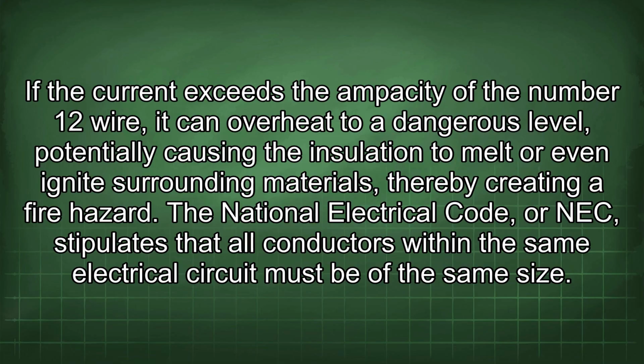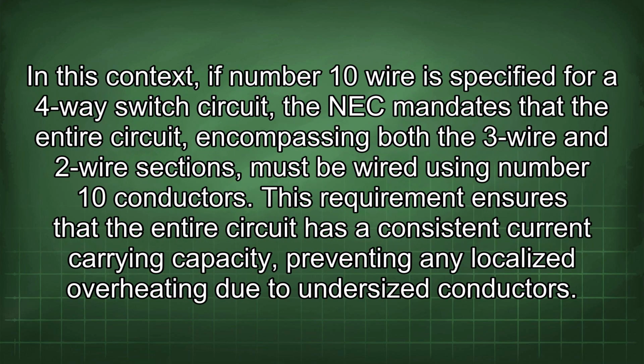The National Electrical Code, or NEC, stipulates that all conductors within the same electrical circuit must be of the same size. In this context, if number 10 wire is specified for a four-way switch circuit, the NEC mandates that the entire circuit, encompassing both the 3-wire and 2-wire sections, must be wired using number 10 conductors.